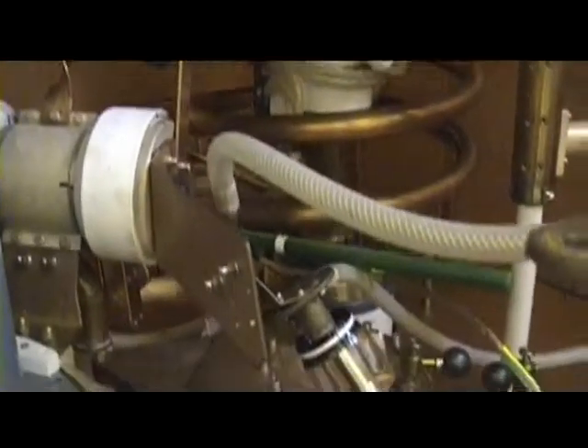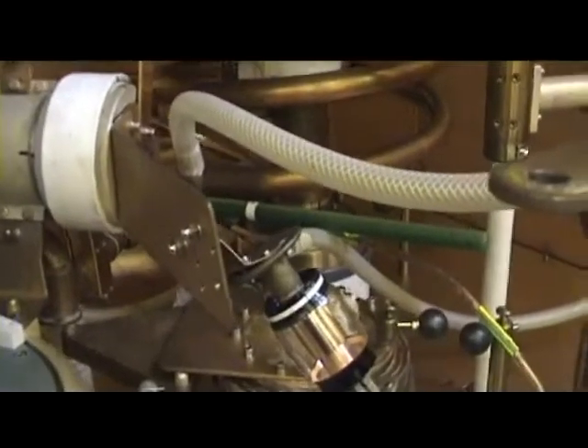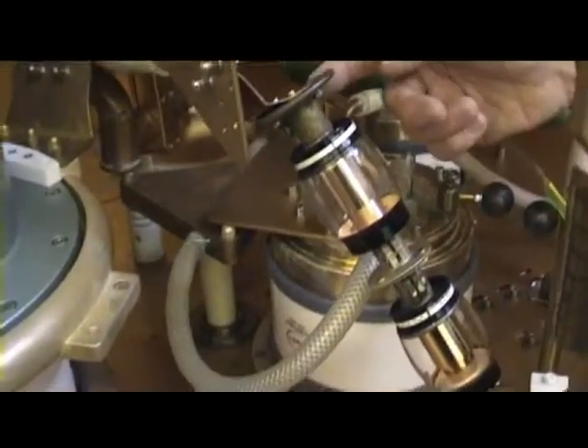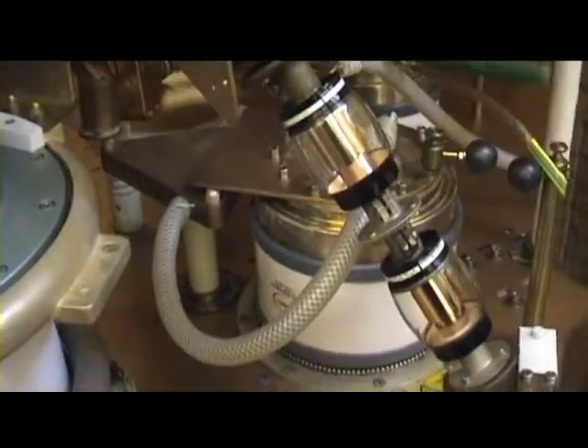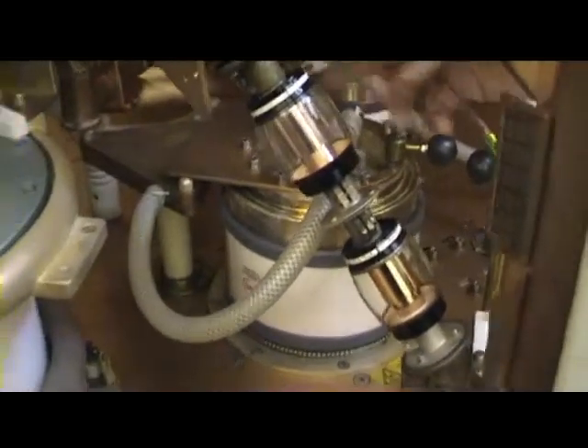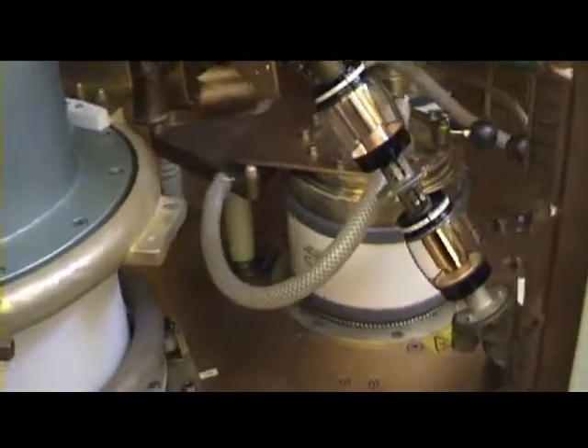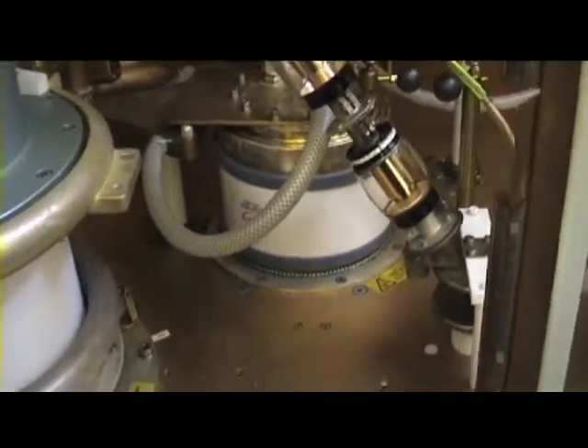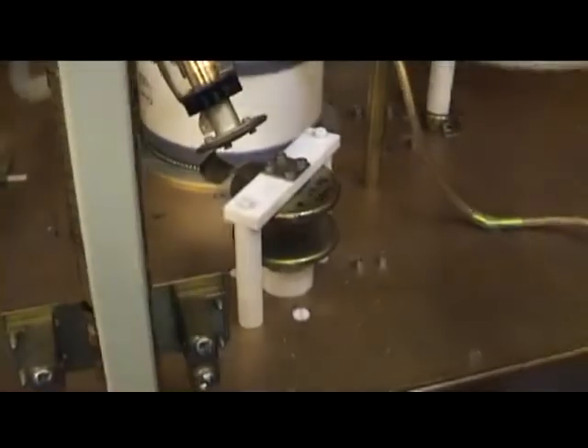The tuning capacitor for it is here on the deck, water cooled. And there's a neutralizing capacitor to send a small amount of RF back to the grid stage via this motorized section here. And it goes back to the grid.